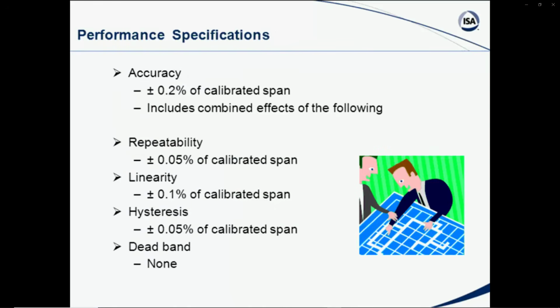Another term you will hear that is fairly common is the overall accuracy. That'll be stated usually in terms of the calibrated span. For instance, plus or minus 0.1% or plus or minus 0.2% of calibrated span. Now that is different. In some cases you could see a device that says the accuracy is plus or minus 1/10 or 0.2 or 1/4% of maximum span. And that would be a completely different situation. So you need to know if it's of calibrated span or is it of maximum span. Typically it's going to be of calibrated span.